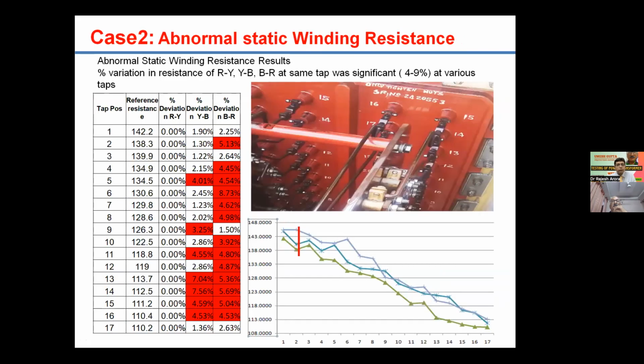Now coming on to the next case, this is also related to the winding resistance measurement. The test was conducted during the preventive maintenance. As sir discussed previously also, when we are measuring the resistance, we should compare the values phase to phase also. For example, let's say at tap number 2 here, I will just see the variation of resistance of RY, YB and BR. So what we noticed for this transformer was that for almost all the tap positions, this variation is more than 3%, which was quite abnormal.